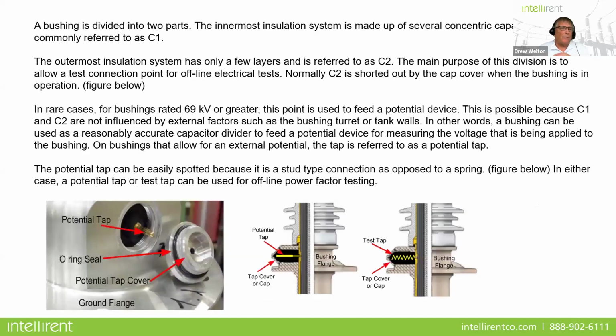Okay, so if we look at the bushing, it's kind of divided into two parts. The innermost insulation of the system is made up of several concentric capacitors, and we refer to that as C1. The outermost insulation of the system has only a few layers, and that's referred to as C2. The main purpose of the division is to allow a test connection point for offline electrical tests. And normally C2 is shorted out by the cap cover when the bushing's in operation.